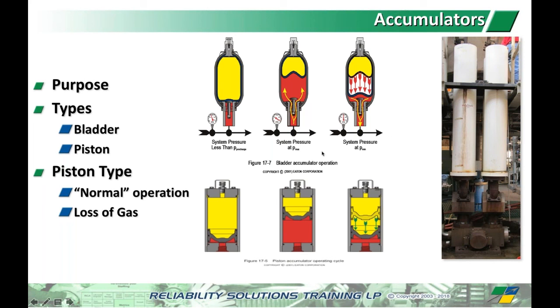These are difficult in any situation because picking leakage here in operation is not easy to do anyway, and usually just involves checking pressures and things like that. And even with ultrasound, I haven't had much success doing anything with that.